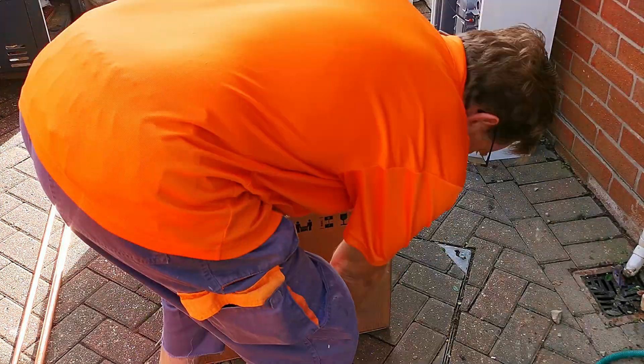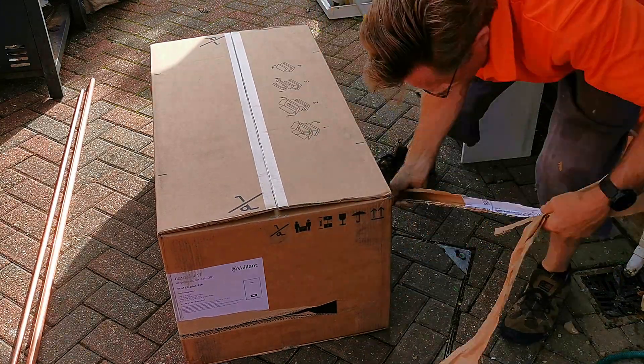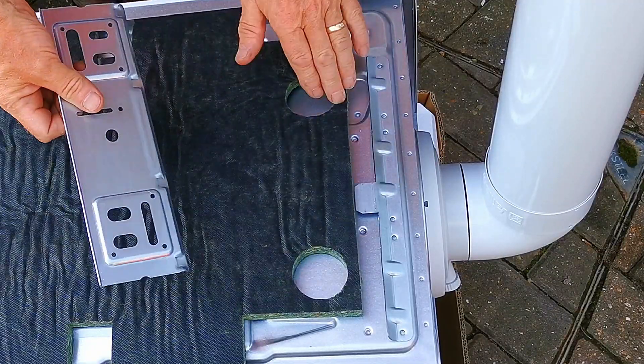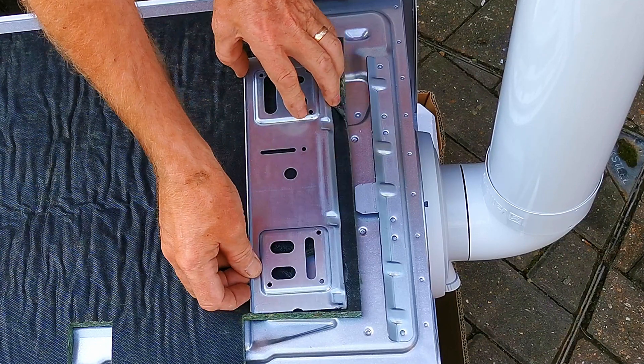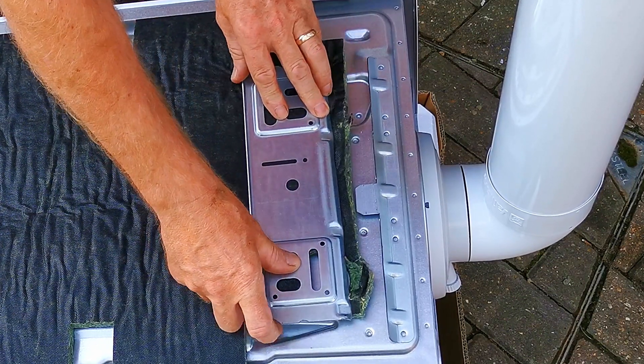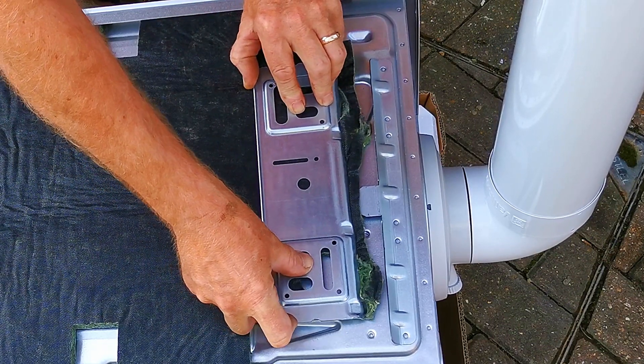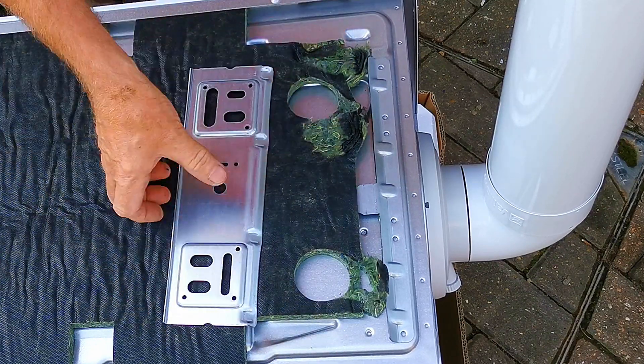Now I've fitted three of the Vaillant ecoTEC plus boilers and I've had the same issues with each installation - the hanging bracket and the insulation on the back of the boiler. Here's the back of the boiler with this thick bit of insulation. What's happening is as I push the boiler up against the wall - and you've got to push it quite hard to get the boiler to engage with the hanging bracket - the insulation is really thick and it's holding the boiler away from the wall. Bits of insulation are breaking off and getting stuck underneath the bracket, then the boiler sits high and doesn't sit squarely on the bracket.